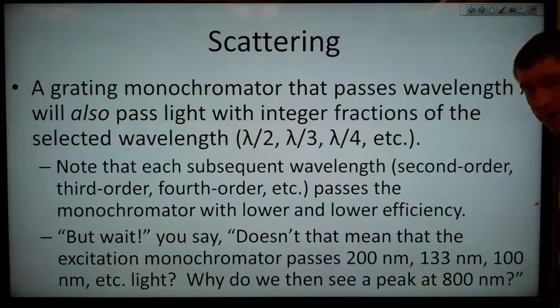But wait, you might say, doesn't that mean that the excitation monochromator passes 200 nanometer light, 133 nanometer light, 100 nanometer light, and so on? Why do we then see a peak at 800 nanometers? And you're right. But the 800 nanometer peak is not an artifact of the excitation monochromator. It's an artifact of the emission monochromator.